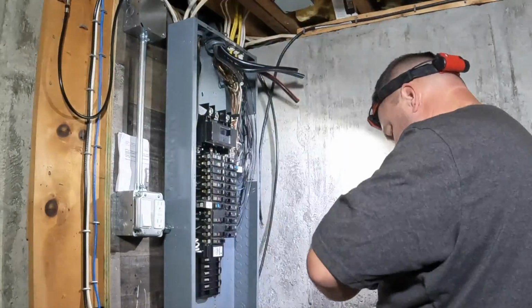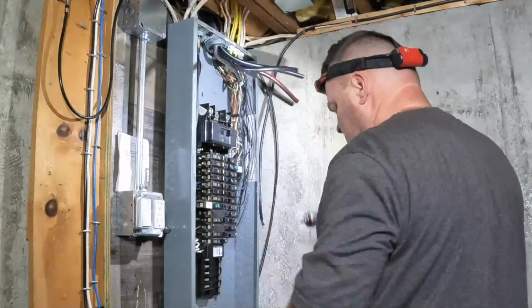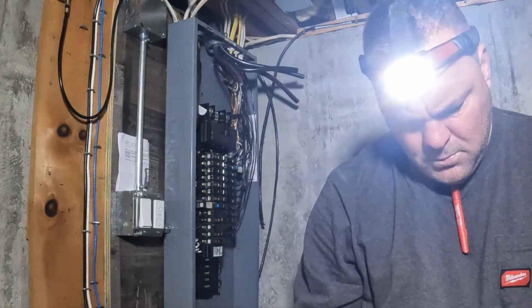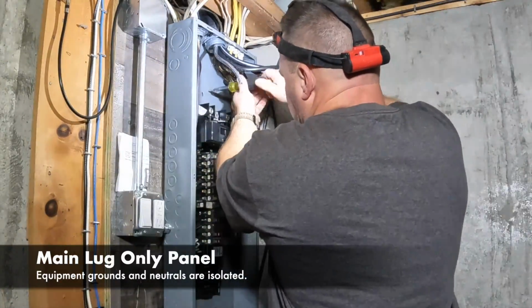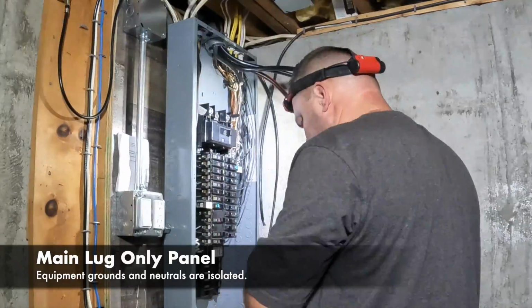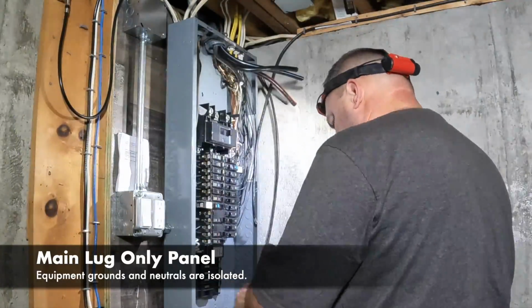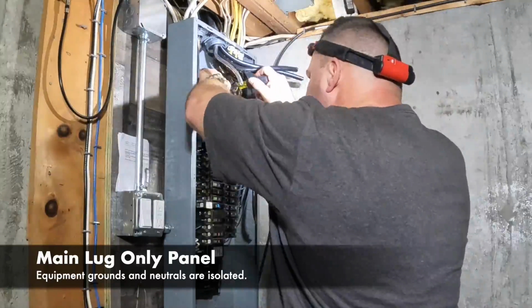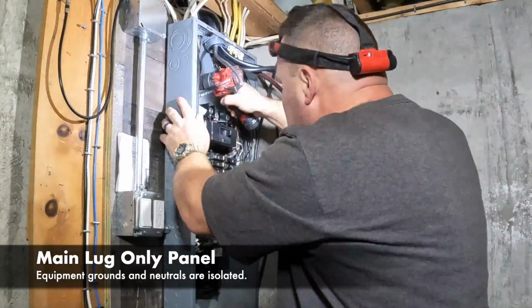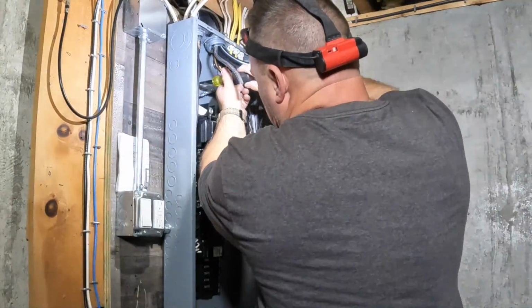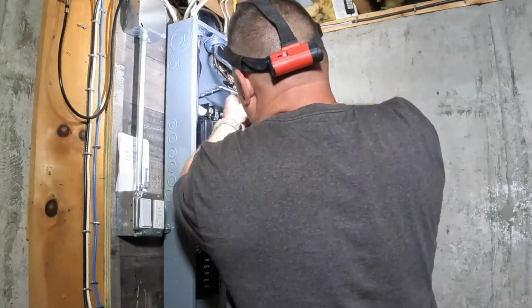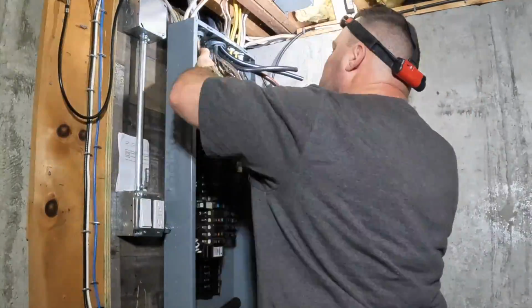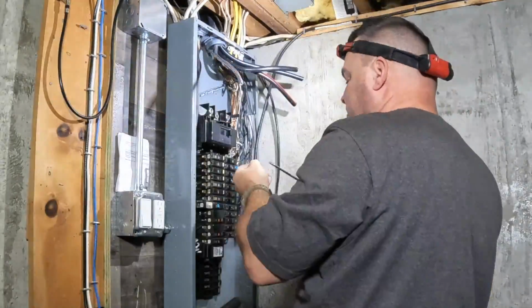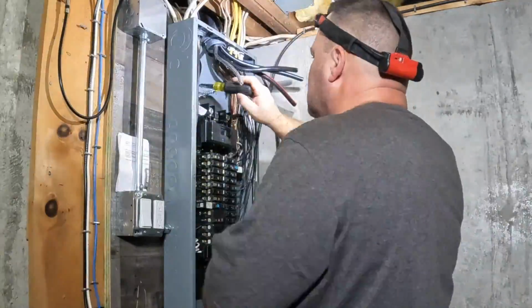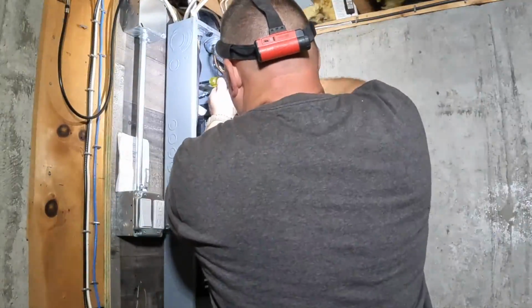But my first order of business is to disconnect the service entrance conductors and install a new equipment grounding bus to physically bond this entire enclosure. And then later on, we'll remove the main bonding jumper, because all of the system bonding is going to be done in the automatic transfer switch, as designed when you're doing a non-separately derived electrical system like this one here.